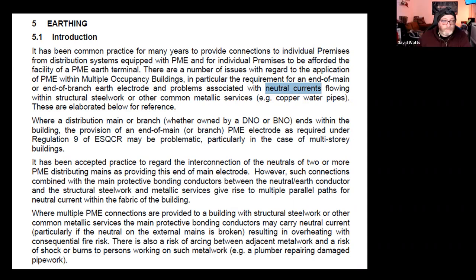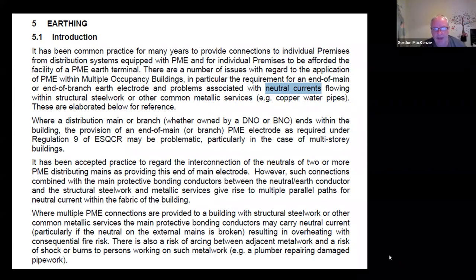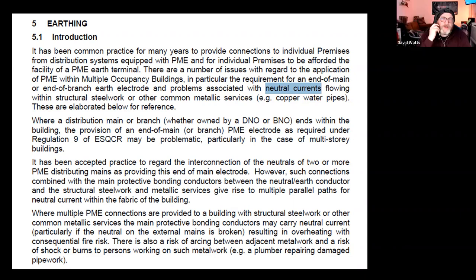Paul, just another wee point on that as well, going back to the original incident that we had in 2014. The contact voltage indicators don't see neutral current diversion. When that's taking place and there's a conductive path there, you will only detect that using a clip-on ammeter. You do not see it. And I think the guidance video that the IET are now working on will show that quite clearly to the guys to make them understand that, that you can absolutely use that on extraneous metalwork contact voltage indicator and it will not see neutral. I mean, you'd only get a voltage once you've created separation, wouldn't you?